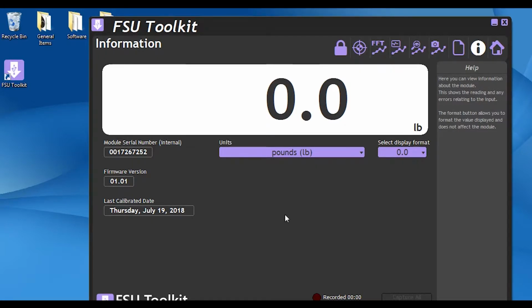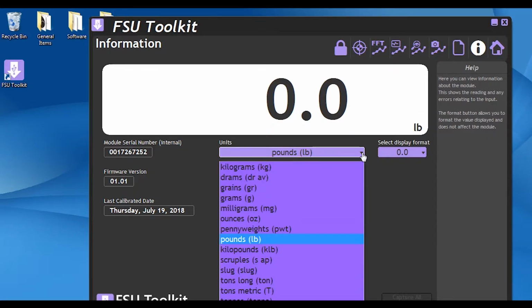If you did not purchase a calibration, the next steps are going to show you how to calibrate with two different methods. The first one we're going to start with is what we call a live load or auto calibration. So the first thing we need to do from this screen is to select the unit of measure. We're going to use pounds here, but just so you know, if you click on this tab, you can select a number of other different measurement types.